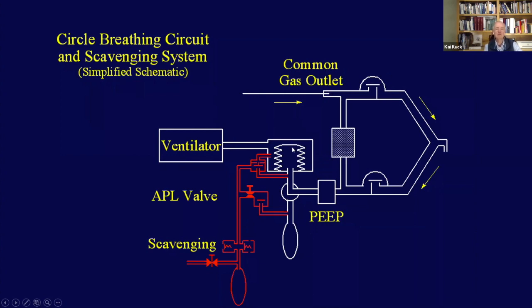This is kind of the old style. There are more modern ways of doing it now. Draeger introduced pistons, for example, and Maquet has a big coil, but that's still kind of the principle. So the box is pressurized from the ventilator for inspiration and pushes down on the bellows. The bellows empty with higher pressure, go through this PEEP valve and then through a CO2 absorber. And then this is a unidirectional valve so that gas only flows in one direction. The fresh gas is getting mixed into this, and then it gets delivered to the patient. The lungs expand. Then the ventilator lets up, and the bellows are allowed to inflate again, and the patient exhales through a unidirectional valve and fills up this bellows.